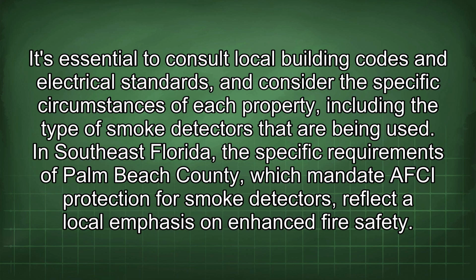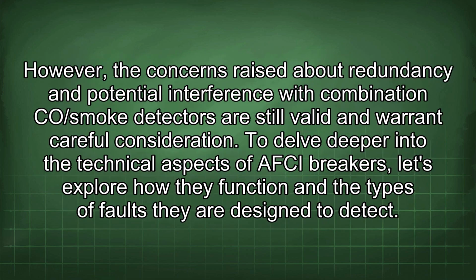In Southeast Florida, the specific requirements of Palm Beach County, which mandate AFCI protection for smoke detectors, reflect a local emphasis on enhanced fire safety. However, the concerns raised about redundancy and potential interference with combination CO/smoke detectors are still valid and warrant careful consideration. To delve deeper into the technical aspects of AFCI breakers, let's explore how they function and the types of faults they are designed to detect.